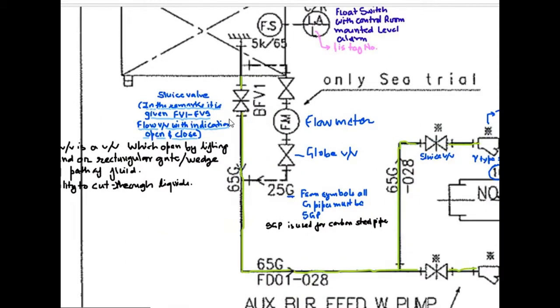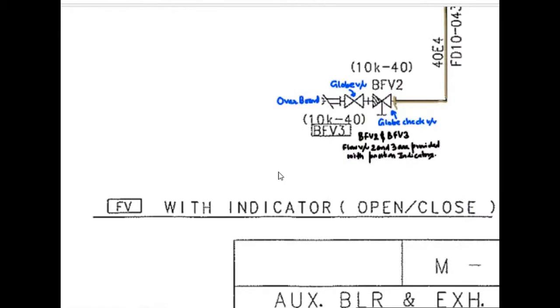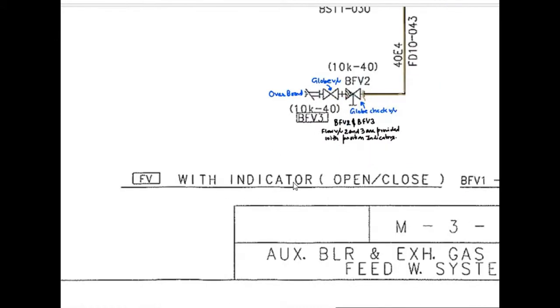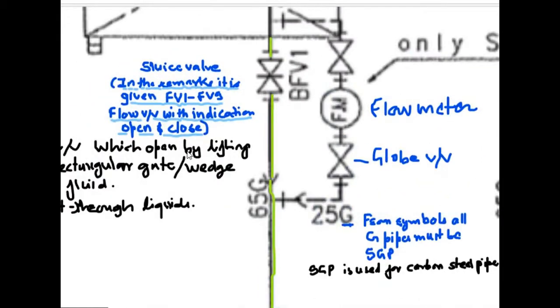So the line from the Cascade Tank is close to a sluice valve. This is the symbol of sluice valve. In the remarks, it is given that flow valve 1 to flow valve 9, that is FV1 to FV9, all the valves are present with position indicators. That is open or closed position. This remark is given here in the corner. Flow valve with indicator open close FV1 to FV9. So this sluice valve has an open and close indication.